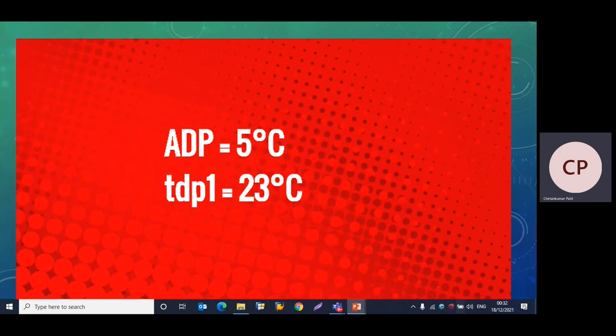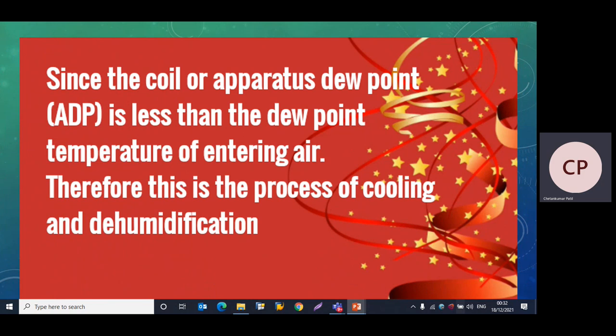The ADP is 5°C and the dew point temperature of entering air at point 1 is 23°C. Comparing these two: the coil's apparatus dew point (ADP = 5°C) is less than the dew point temperature of the entering air (23°C). Therefore, this is the process of cooling and dehumidification.